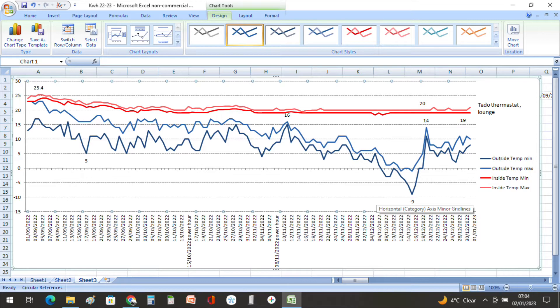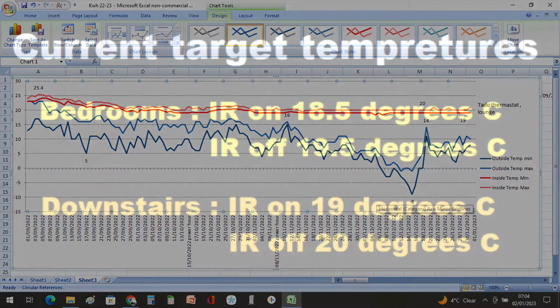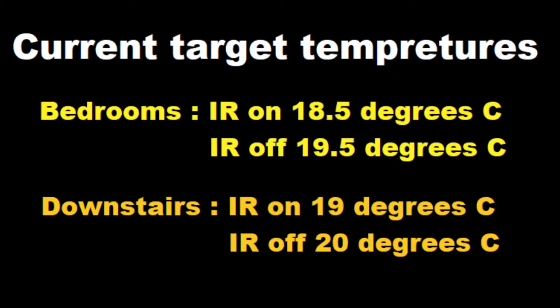Now the internal target temperatures, the bedrooms, so that's all the upstairs really, are set between 18 and a half degrees. So the infrared heaters turn on at 18 and a half degrees and they go off at 19 and a half degrees. And the downstairs temperatures, the infrared heaters come on at 19 degrees and they go off again at 20 degrees.